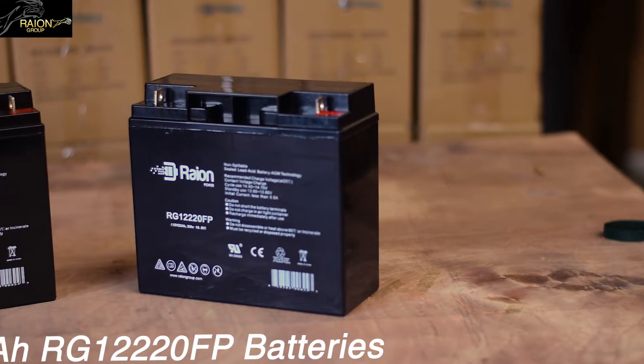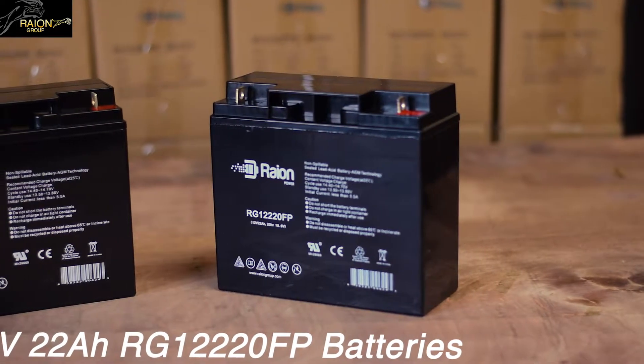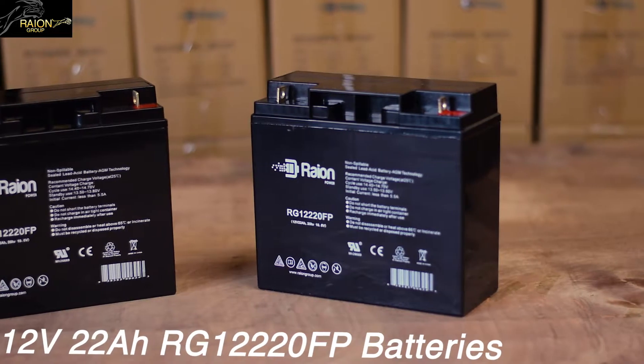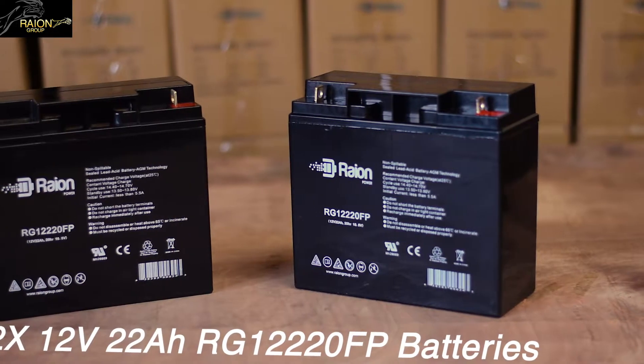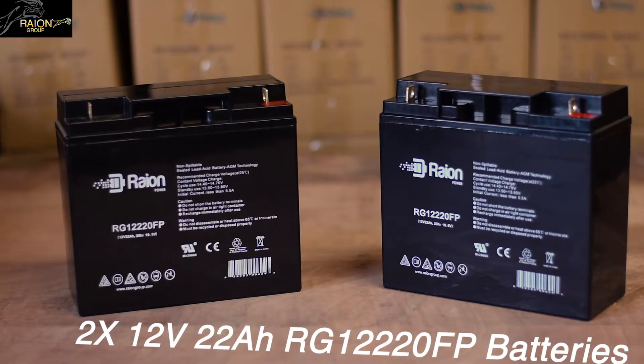You will require two 12 volt 22 amp hour batteries with FP terminals. We are using Raion Power's RG12220FP batteries. These batteries will actually give our APC UPS systems a longer run time when compared to the standard 18 amp hour batteries.